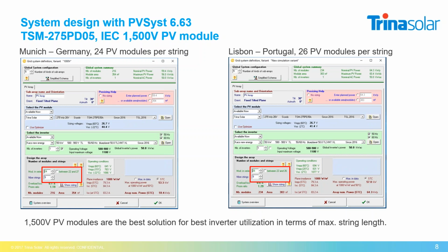Now, what happens if I switch to a 1500 volt module? It's exactly the same type, the same polycrystalline module with the same power range. The only difference is that it has a different certification. The 1500 volt module is certified for system voltages up to 1500 volt. If I now take a look at the string design, you can directly see that for Munich, before it was from 22 to 24, now it's from 22 to 27. You can see it here on the left-hand side.